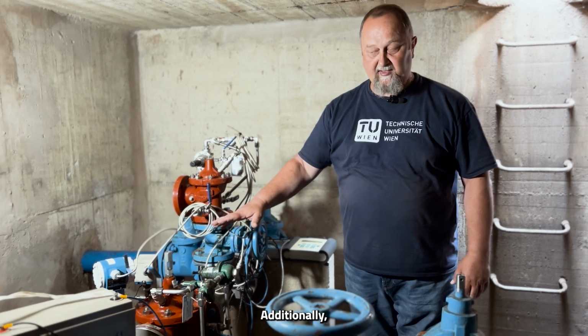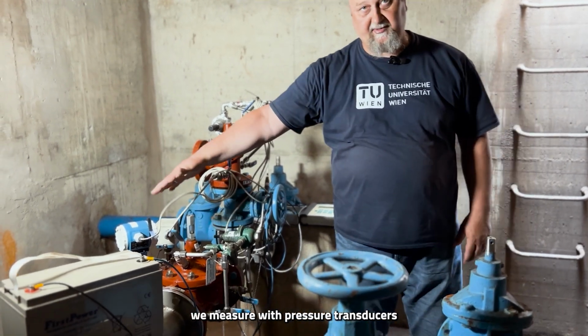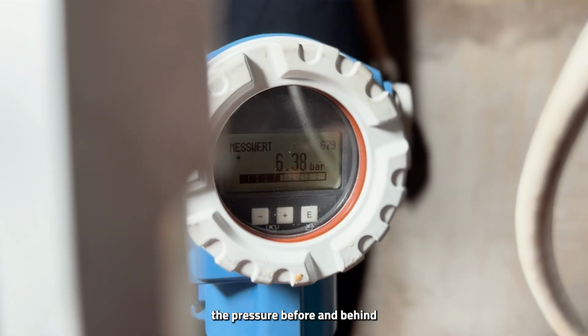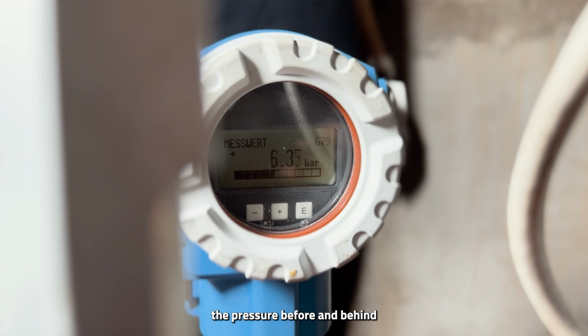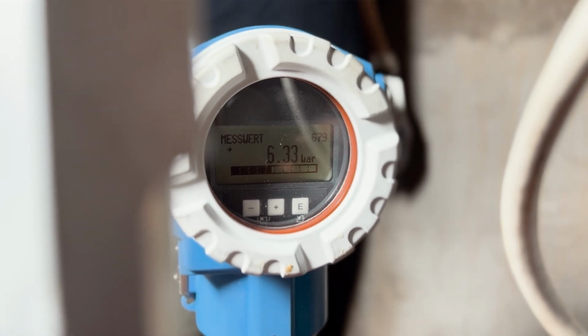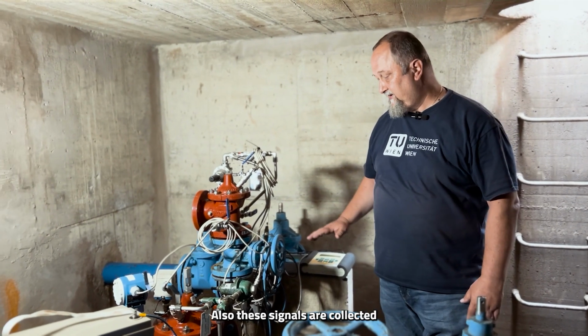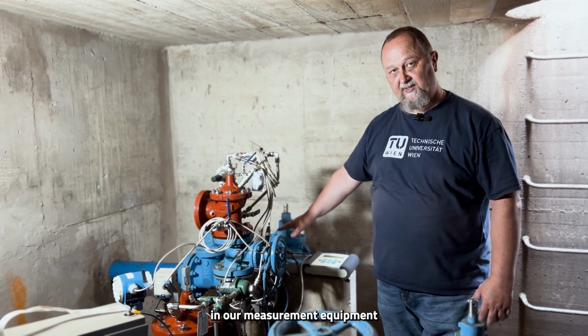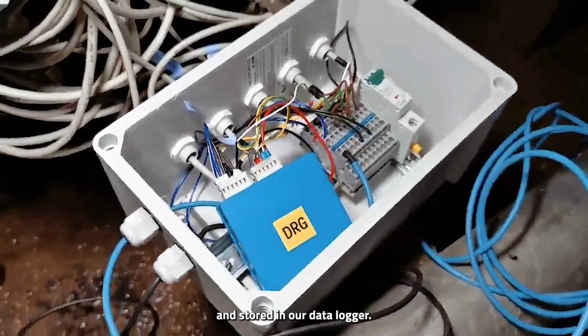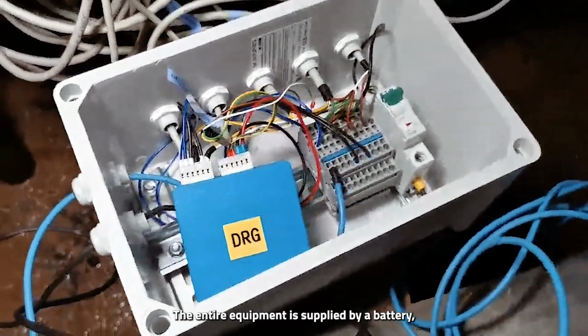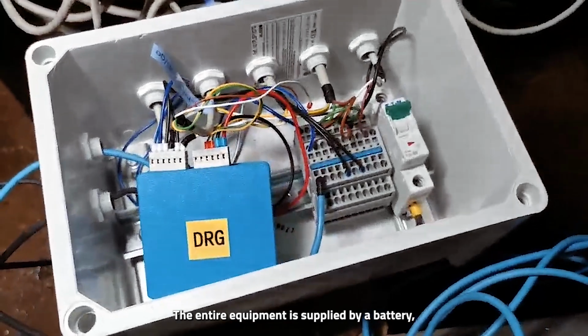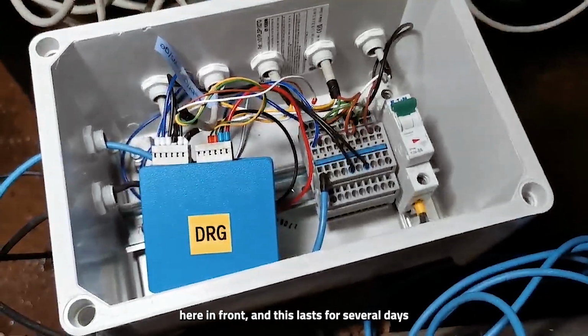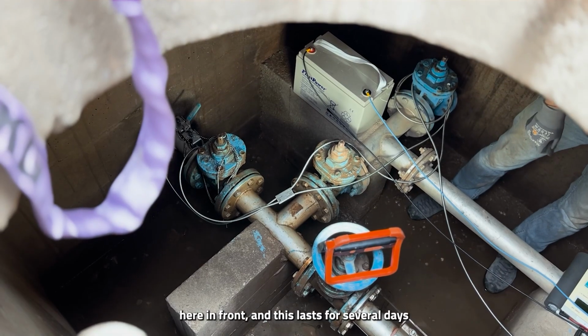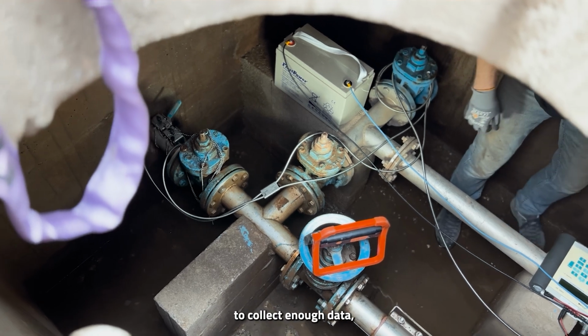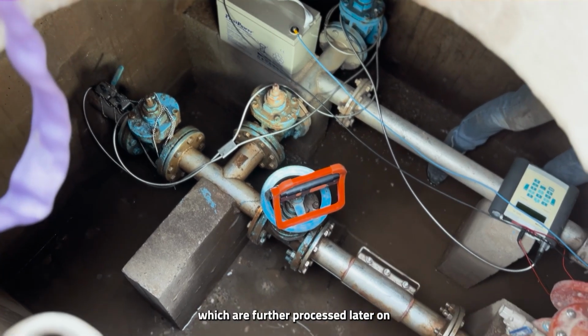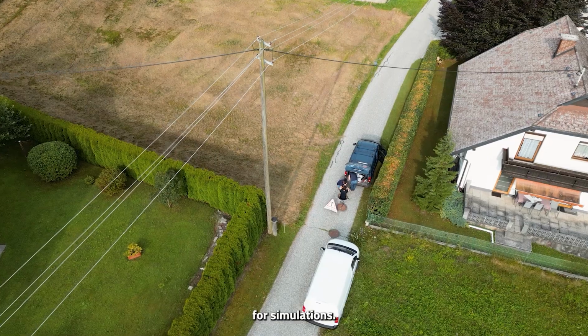Additionally, we measure with pressure transducers the pressure before and behind the pressure reduction valve. Also, these signals are collected in our measurement equipment and stored in our data logger. The entire equipment is supplied by a battery in front, and this lasts for several days to collect enough data which are further processed later on for simulations.